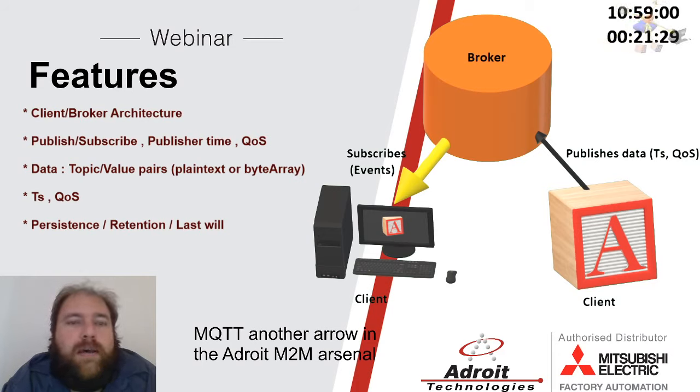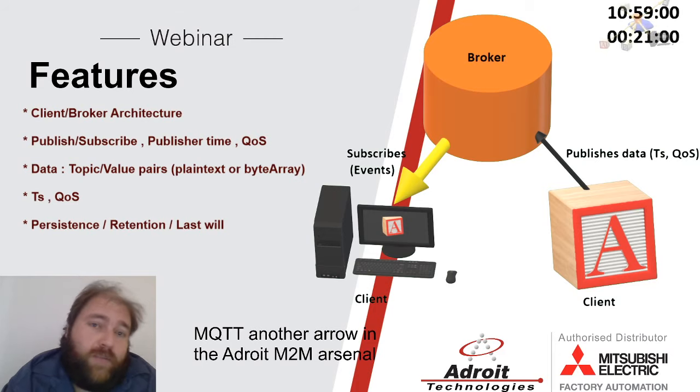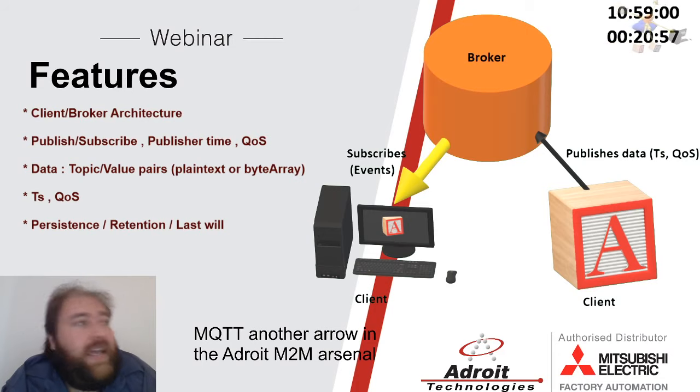So this enables one of the primary things that M2M does, but in a different way, and that's part of my comparison. M2M will create a connection to the SCADA server and thereby send data through as events, but then the SCADA holds that connection and it can transmit back down. MQTT does something different. It implements a broker.